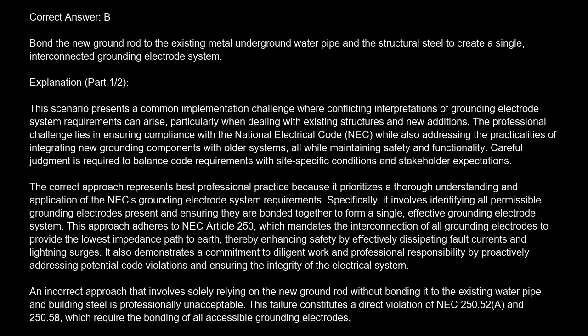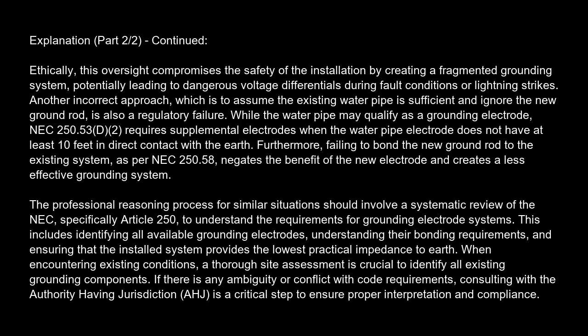This failure constitutes a direct violation of NEC 250.52(A) and 250.58, which require the bonding of all accessible grounding electrodes. Ethically, this oversight compromises the safety of the installation by creating a fragmented grounding system, potentially leading to dangerous voltage differentials during fault conditions or lightning strikes. Another incorrect approach, which is to assume the existing water pipe is sufficient and ignore the new ground rod, is also a regulatory failure. While the water pipe may qualify as a grounding electrode, NEC 250.53(D)(2) requires supplemental electrodes when the water pipe electrode does not have at least 10 feet in direct contact with the earth. Furthermore, failing to bond the new ground rod to the existing system, as per NEC 250.58, negates the benefit of the new electrode and creates a less effective grounding system.